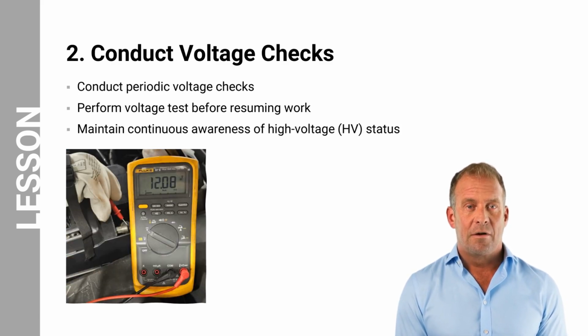Number 2, conduct voltage checks. The frequency of voltage checks should be determined based on the specific work performed and the manufacturer's recommendations. Voltage checks may need to be conducted periodically throughout the work, especially if the work involves multiple steps or interruptions. Whenever there is a work interruption, such as taking a break or temporarily leaving the work area, perform a voltage check before resuming work. This is especially important if any electrical system or component changes have occurred during the interruption.